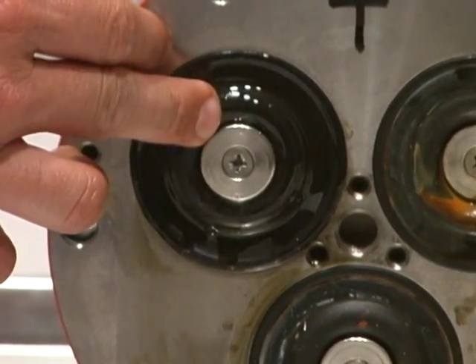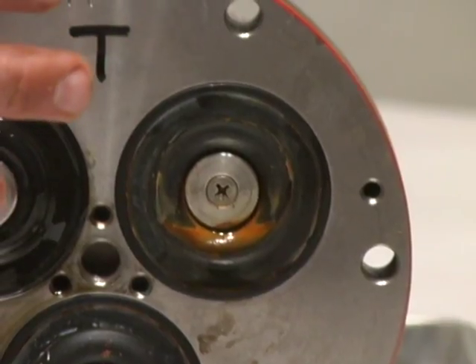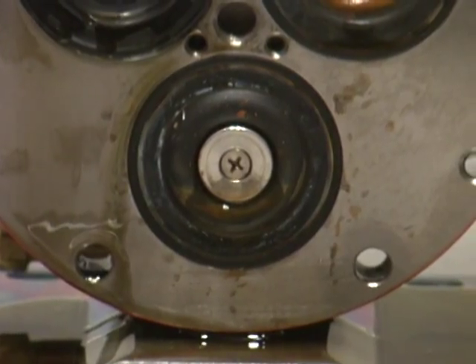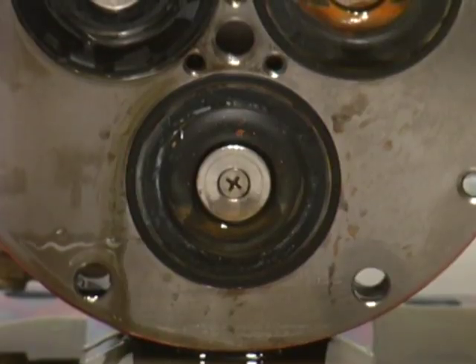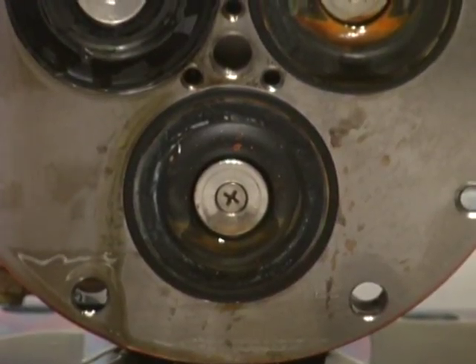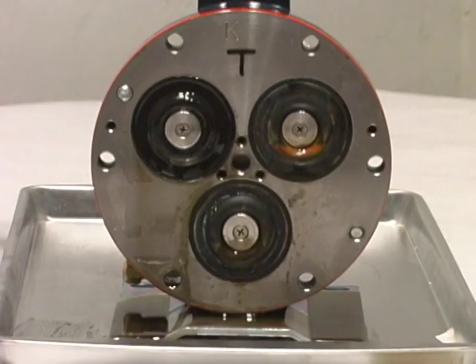There are three diaphragms that cause the pump to move fluid. Visually inspect each diaphragm to see if any or all need to be replaced. There may have been deformation of the diaphragm due to increased pressure or impurities in the material that came through and damaged the diaphragm. Typically, if there is a damaged diaphragm, it is because during pump operation material was leaking out.